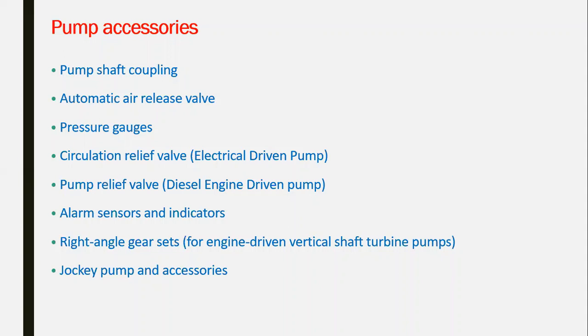It's a relief valve. If you notice, last time we talked about the electrical driven pump, which doesn't require a pump relief valve. The electrical driven pump has the advantage that you can control the speed and the pressure of the pump by using variable frequency drive and the electrical controller for the motor pump. Different than the diesel engine driven pump, which doesn't have this facility of speed control and pressure control. That's why it requires a pump relief valve to discharge the excess amount of water from the network because of the continuous operation of the pump without discharge. And the alarm sensor and the indicators, from the definition, they are the alarm devices.